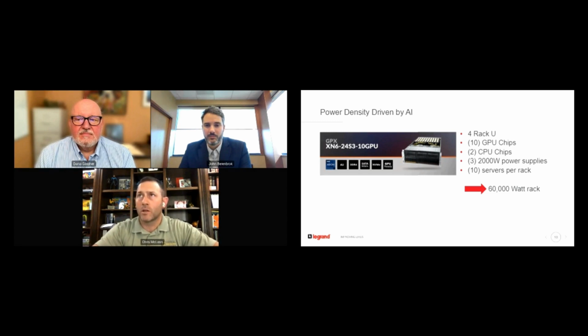But what we're getting for RFPs right now are trending from 1,600 watts per U to 3,200 watts per U. And what John was talking about earlier, we're not talking about 30 amp 3-phase per rack. We're talking about multiple 100 amp 3-phase per rack now. From a power standpoint, we could throw a lot more copper and a lot more busway at these things and get the blinky lights to blink.